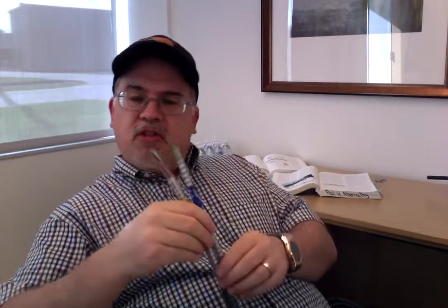So the first one we want to look at is normal interlocked type MC cable. Now, of course, MC cable comes in corrugated, smooth, or interlocked. Interlocked is what we produce, so we're going to talk about the interlocked, which is probably the most widely used type MC cable in the industry. All right, now, these two products here are both MC. It just so happens that one of them has a steel armor and the other one has an aluminum armor. Now, UL 1569 lets us construct it whether it has an aluminum or steel armor.